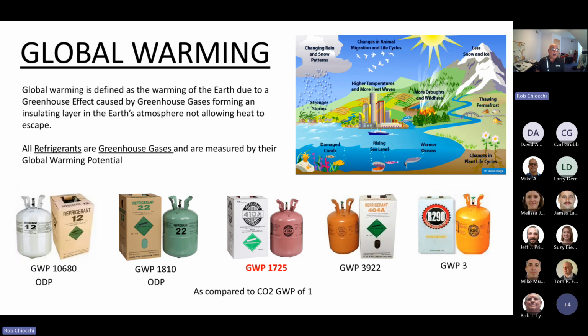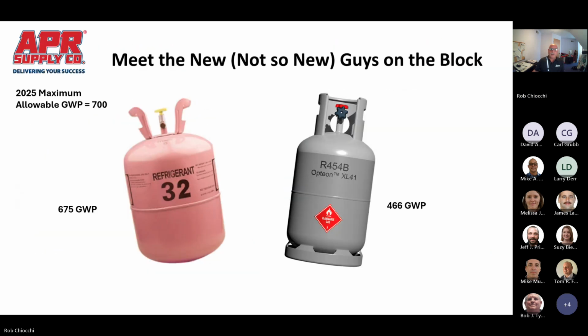That thing that has to be done is we are now going to change to a low global warming potential refrigerant. What refrigerants are those? Well, the industry pretty much has chosen between 2 refrigerants. They're new here in the United States, but they're really not so new in the global footprint. R32 and refrigerant R454B have been used in Europe and Asia quite extensively, probably over the last 10 years. They both are superior refrigerants to R410A in their ability of heat absorption per weight. So we're actually able to achieve higher efficiencies at a lower refrigerant charge by volume with these 2 refrigerants.